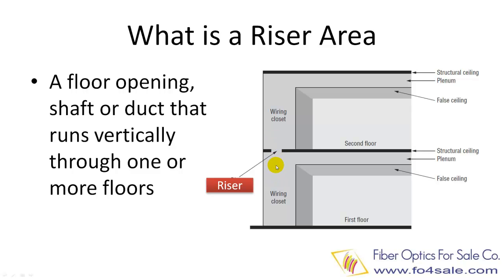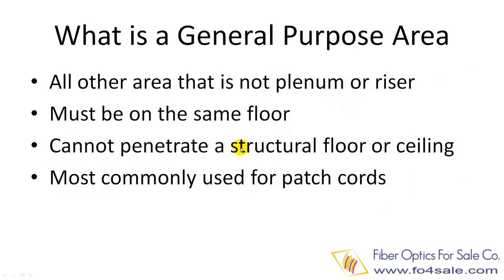In order to prevent fire from passing from one floor to another, fiber cables used in riser areas must have certain fire resistant qualities. The next fire rating area is called general purpose area. Typically, all other areas inside a building which is not a plenum or a riser area is a general purpose area. General purpose area is within a floor — it cannot penetrate a structural floor or ceiling. This rating is the most commonly used for fiber patch cords, since patch cords are not supposed to go through a floor or ceiling.